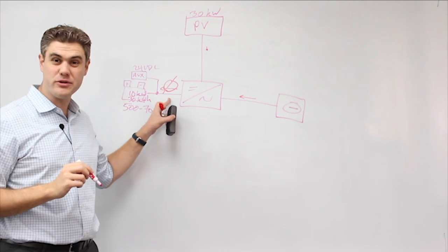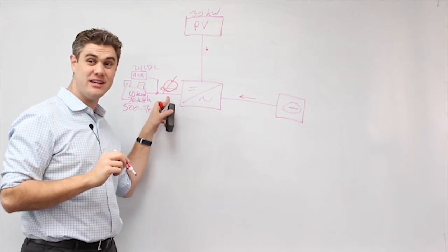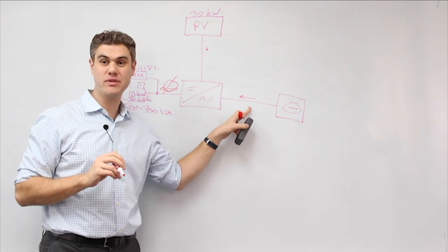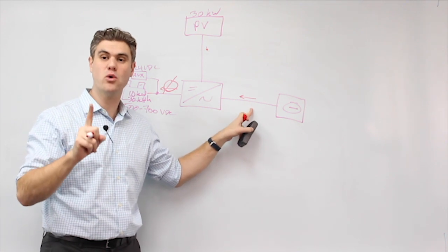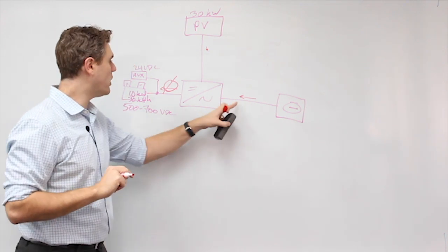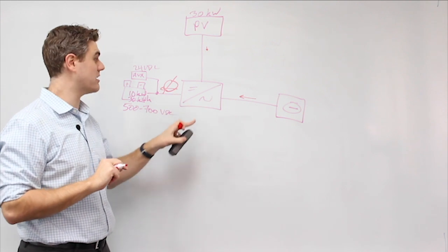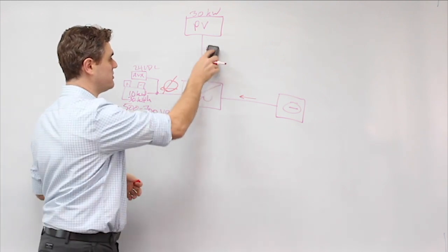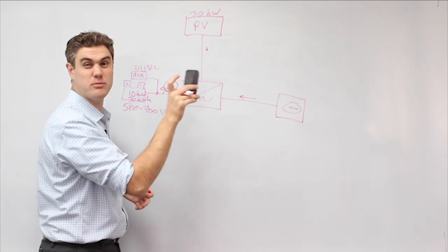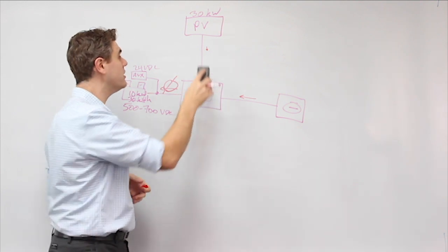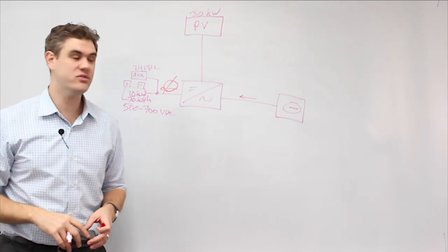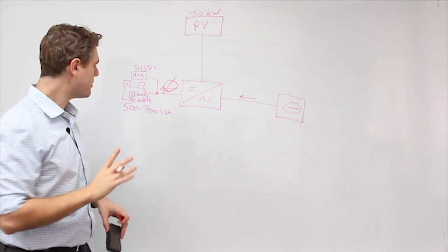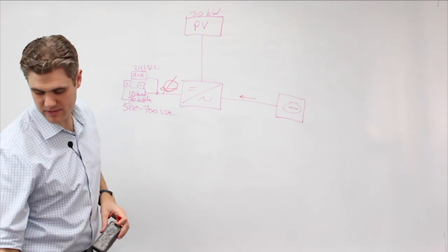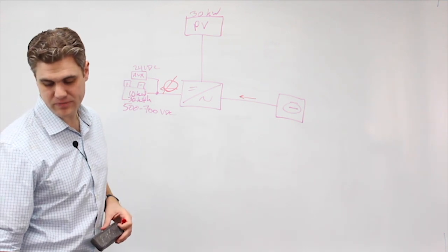Because remember the golden rule, you cannot charge from the grid just to discharge to the grid at a later time. And we're going to take a non-import approach to this problem. We want to prevent this scenario right here from ever happening, whether the solar is on a little bit, early morning, late afternoon, or just cloudy, or even if it's at nighttime and off. This cannot be allowed to happen. So here's how we're going to fix it. This is how we're going to prevent it.